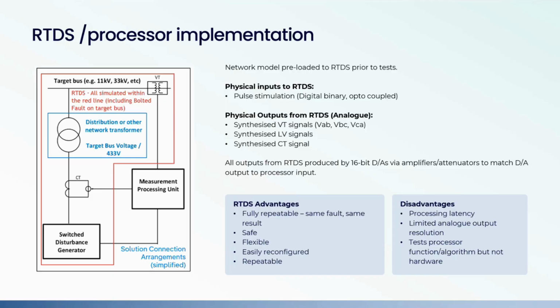And here's how it works. A network model, in this case a section of Spen's distribution network in Liverpool, is loaded into the simulator prior to the tests. Our model contained 132 kV grid supply points, multiple 33 and 11 kV interconnected substation features, and ran down to LV. The network can be simulated entirely on the RTDS, and bolted faults can be applied and current examined at any chosen node, so we can actually obtain fault level results for both peak make and RMS break, the two key parameters, very easily.